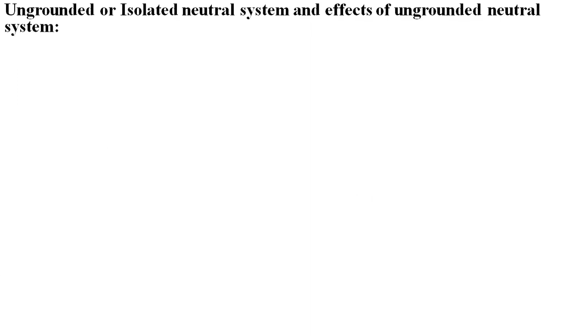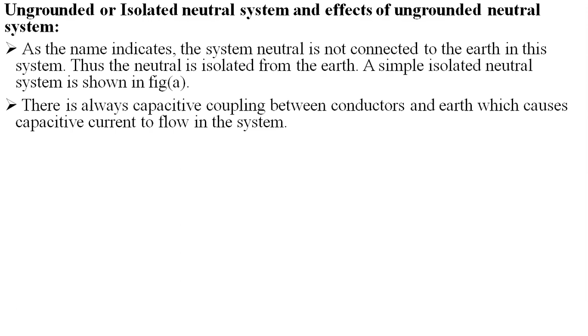Ungrounded or isolated neutral system, and the effects of this ungrounded neutral system will be observed here. As the name indicates, the system neutral is not connected to the earth in this system. Thus, the neutral is isolated from the earth and a simple isolated neutral system can be observed here. There is always a capacitive coupling between the conductors and the earth, which causes capacitive current to flow in the system. And the line conductors have capacitance between one another and to the earth.